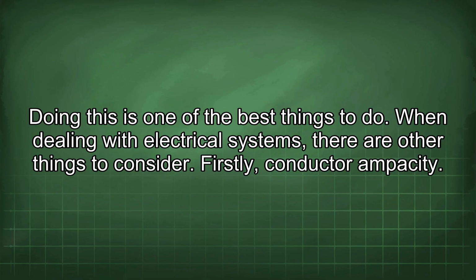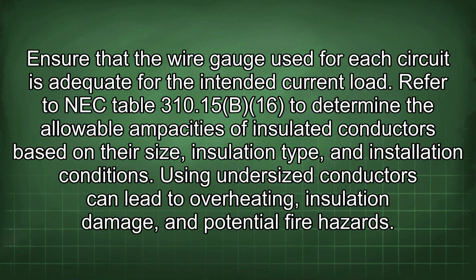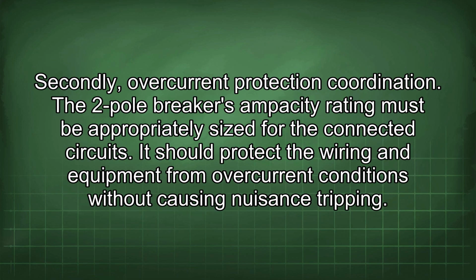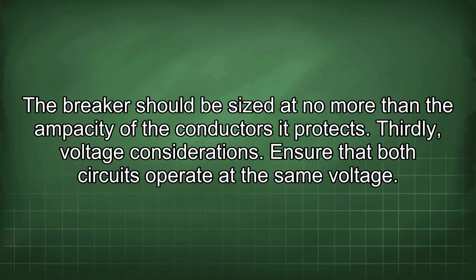When dealing with electrical systems, there are other things to consider. Firstly, conductor ampacity. Ensure that the wire gauge used for each circuit is adequate for the intended current load. Refer to NEC Table 310.15(B)(16) to determine the allowable ampacities of insulated conductors based on their size, insulation type, and installation conditions. Using undersized conductors can lead to overheating, insulation damage, and potential fire hazards. Secondly, overcurrent protection coordination. The two-pole breaker's ampacity rating must be appropriately sized for the connected circuits. It should protect the wiring and equipment from overcurrent conditions without causing nuisance tripping. The breaker should be sized at no more than the ampacity of the conductors it protects.